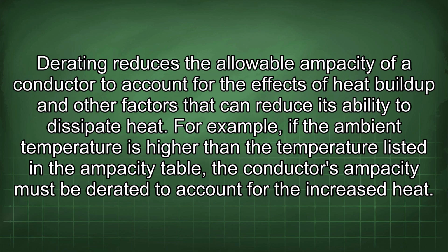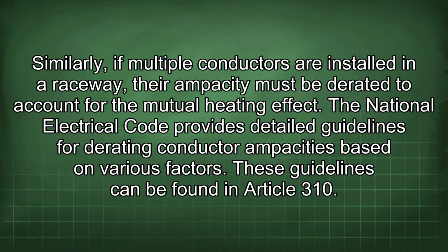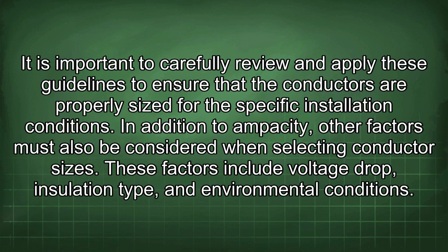For example, if the ambient temperature is higher than the temperature listed in the ampacity table, the conductor's ampacity must be derated to account for the increased heat. Similarly, if multiple conductors are installed in a raceway, their ampacity must be derated to account for the mutual heating effect. The National Electrical Code provides detailed guidelines for derating conductor ampacities based on various factors. These guidelines can be found in Article 310. It is important to carefully review and apply these guidelines to ensure that the conductors are properly sized for the specific installation conditions.